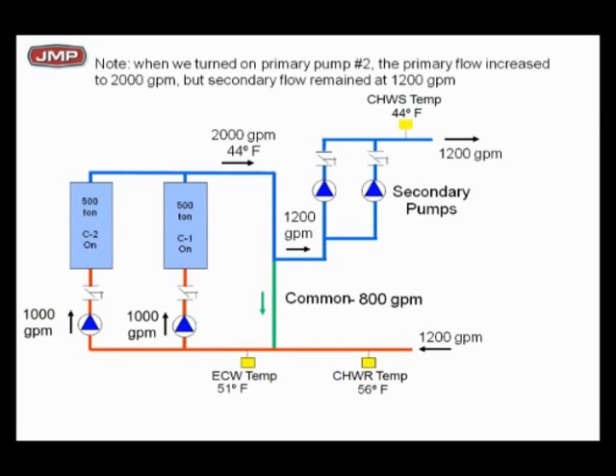I've got two chillers running now. Everybody's happy. I'm keeping 44-degree water to my chill water coils. Everything is fine. And the good news is I got that 56 hot return water coming back. Now, I want to play with that 56 degree return water a little bit so you can understand this term, low delta T syndrome. I want you to kind of have a feeling for that.